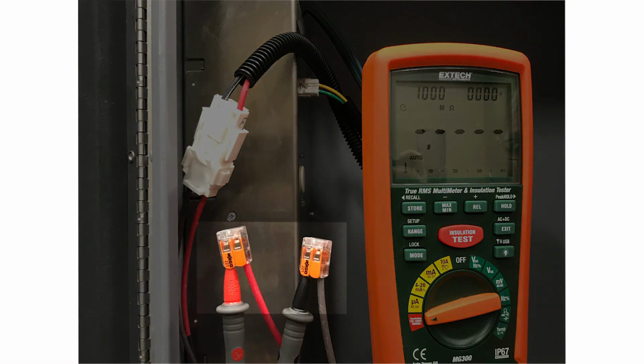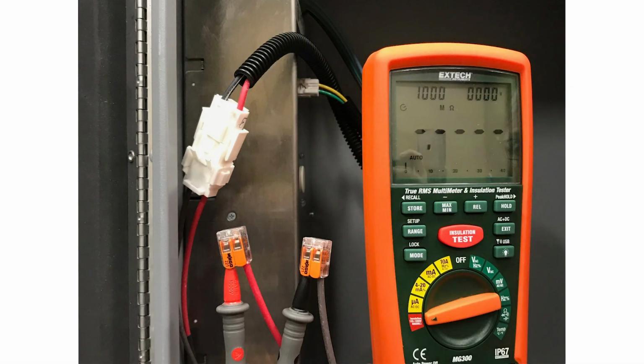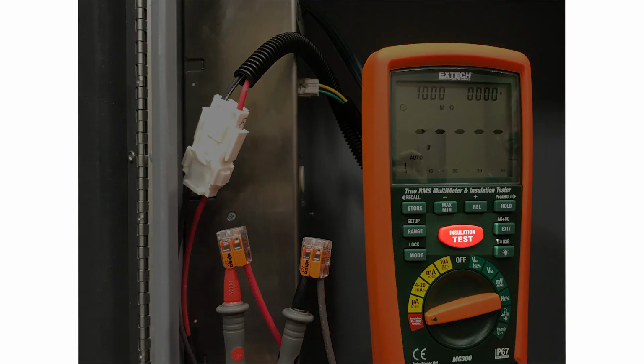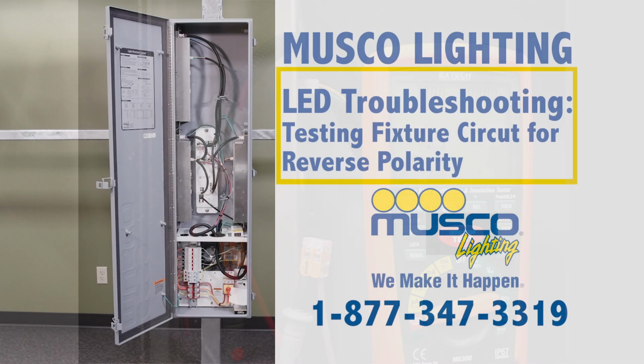Hook your meter up red to red and black to black, then press the insulation test button and hold for 45 seconds, recording both resistance and voltage if your meter gives you a voltage reading. Testing will cause a good fixture to glow, but it may not be visible from the testing location.